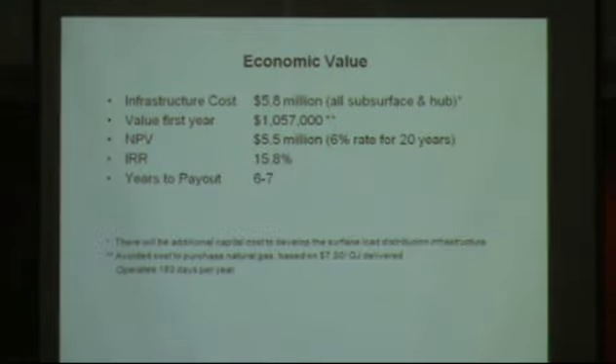The value of this is equivalent to the amount of natural gas we don't have to purchase, and the avoided cost in the first year is about $1 million. We based that value, when we did this assessment a couple of years ago, on the SaskEnergy 5-year contract delivered price for natural gas, which was $7.50 per gigajoule. We used that number to set our forecasts, and this also relates to operating only 183 days per year, about half the year at capacity. The net present value on that cash flow stream is about $5.5 million, based on a 6% discount rate over 20 years, a rate of return of just under 16%, and a payout period of 6 to 7 years.